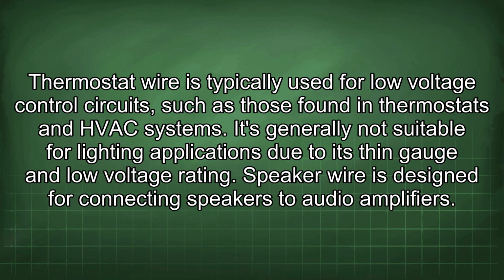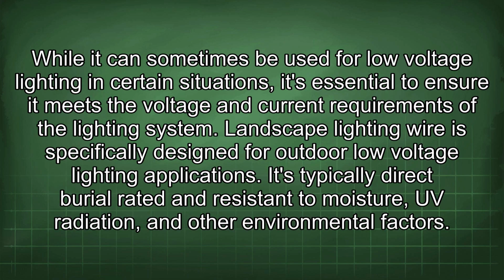Speaker wire is designed for connecting speakers to audio amplifiers. While it can sometimes be used for low voltage lighting in certain situations, it's essential to ensure it meets the voltage and current requirements of the lighting system. Landscape lighting wire is specifically designed for outdoor low voltage lighting applications. It's typically direct burial rated, and resistant to moisture, UV radiation, and other environmental factors.